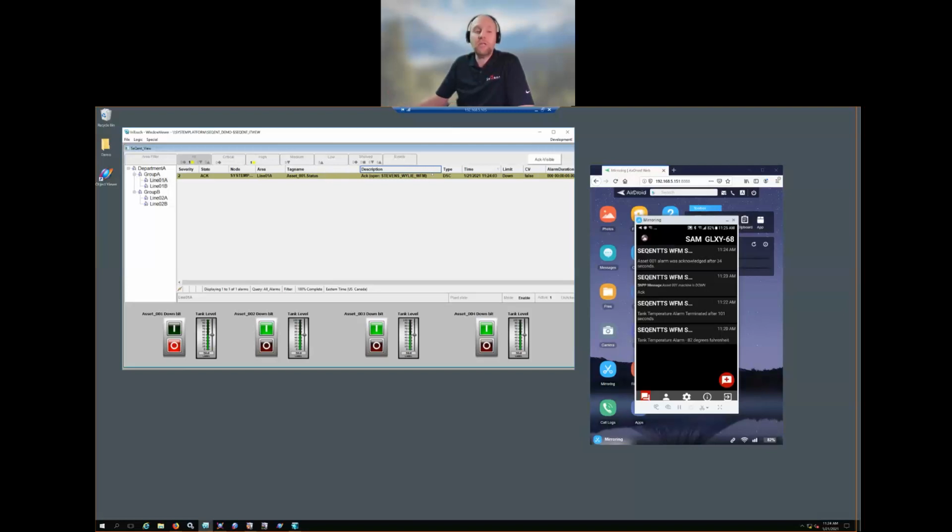Now, what's somewhat interesting about that is not necessarily our software just responding to the message from the end device. It is actually our software going what we call around the horn, delivering it to the system platform environment, the data source, and waiting for it to tell us that that alarm is acknowledged. So that message to the end user is really confirmation that that acknowledgement did get all the way back to the data source and then is delivered back to that end user once again as confirmation that acknowledgement occurred.